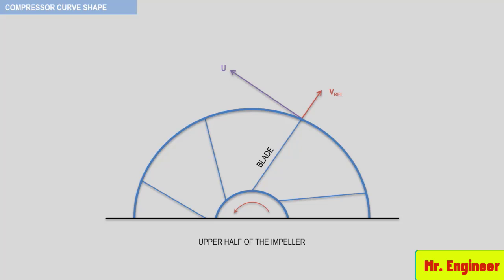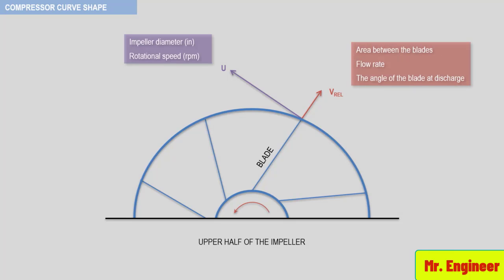The blade tip velocity is a function of the diameter of the blade and the blade rotational speed. The velocity relative to the blade is a function of the area between the blades, the flow rate at that location, and the angle of the blade at the discharge of the impeller. For this discussion, we assume that the velocity relative to the blade exactly follows the blade angle — that is, the slip is equal to zero. This assumption can be used since it will not impact the final conclusion of our discussion.